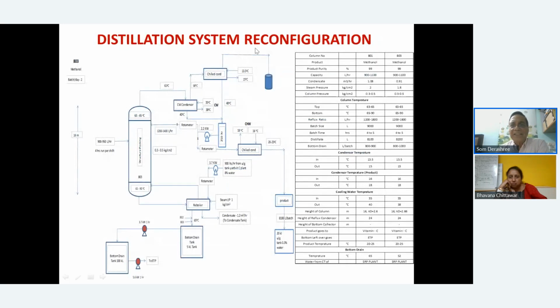This is another distillation system. Again, what has happened is the condenser, because the distillation column is 16 meter long, was almost at 20 meter height, and all the cooling water was going up to the condenser. The rest of the system was at the ground floor only, and so was the chill water, because these are all low boiling solvents being recovered. So they come here, and after the condenser they go to chill water. They want to recover everything whatever is possible. So this was a system with very high requirement.